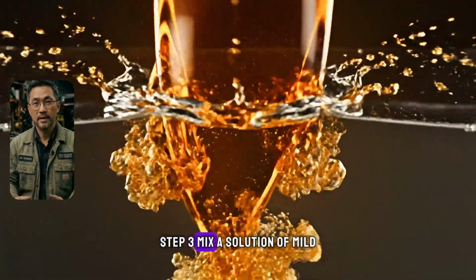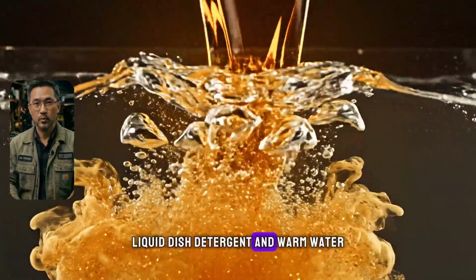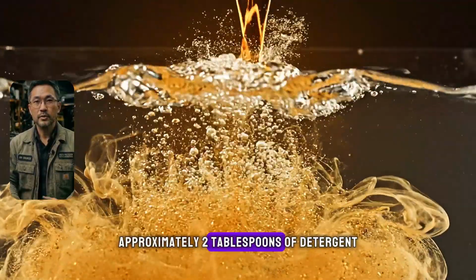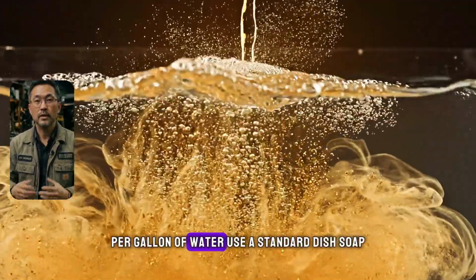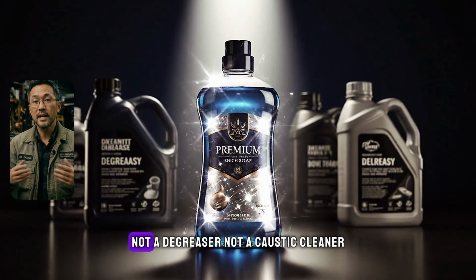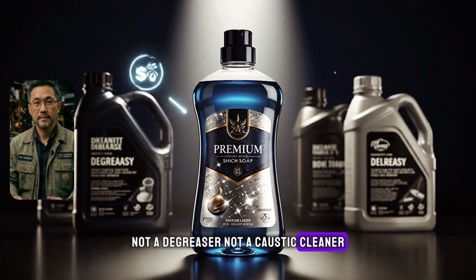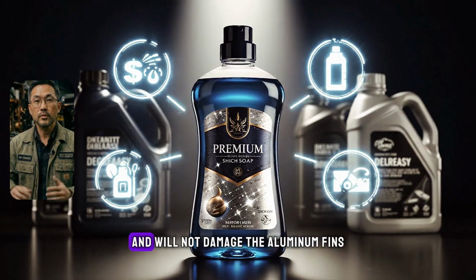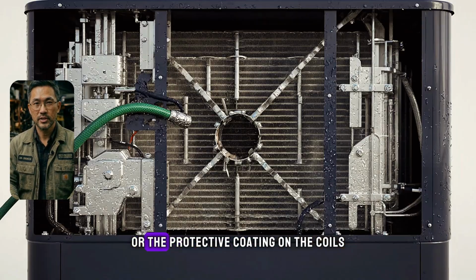Step 3. Mix a solution of mild liquid dish detergent and warm water. Approximately 2 tablespoons of detergent per gallon of water. Use a standard dish soap, not a degreaser. Not a caustic cleaner. Mild detergent is pH neutral and will not damage the aluminum fins or the protective coating on the coils.